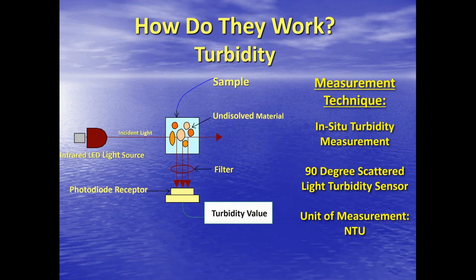it's very repeatable. I won't say it's very accurate. It is pretty accurate, but not as most of you understand turbidity. If you deal in a drinking water plant with benchtop turbidimeters, you're measuring out a couple of decimals of an NTU. We don't really care about that level of accuracy. We just want to understand the trend and when that wash water is trending clean.